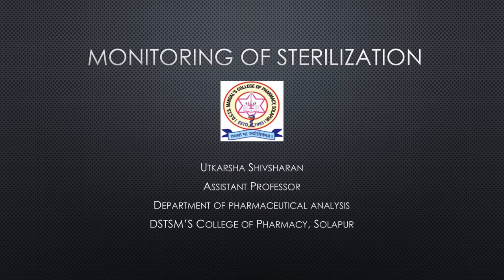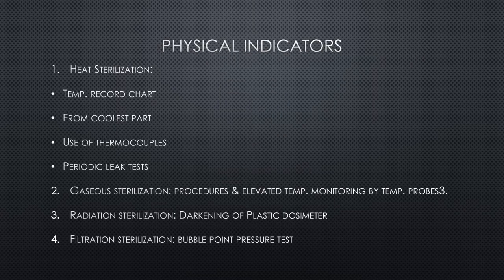To check the assurance of sterilization, monitoring is carried out by means of different types of indicators. We will see them one by one. For physical indicators, if we take the heat sterilization process, a temperature record chart is made for each heat sterilization cycle. This cycle can be maintained for dry heat sterilization as well as moist heat sterilization. It is recommended that the temperature should be taken from the coolest part of the loaded sterilizer for heat distribution and penetration.